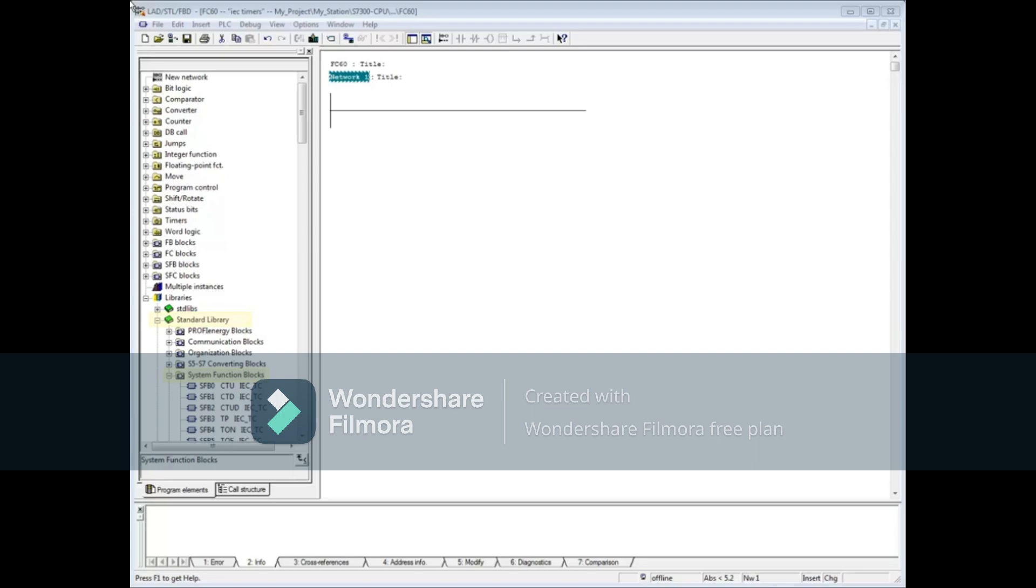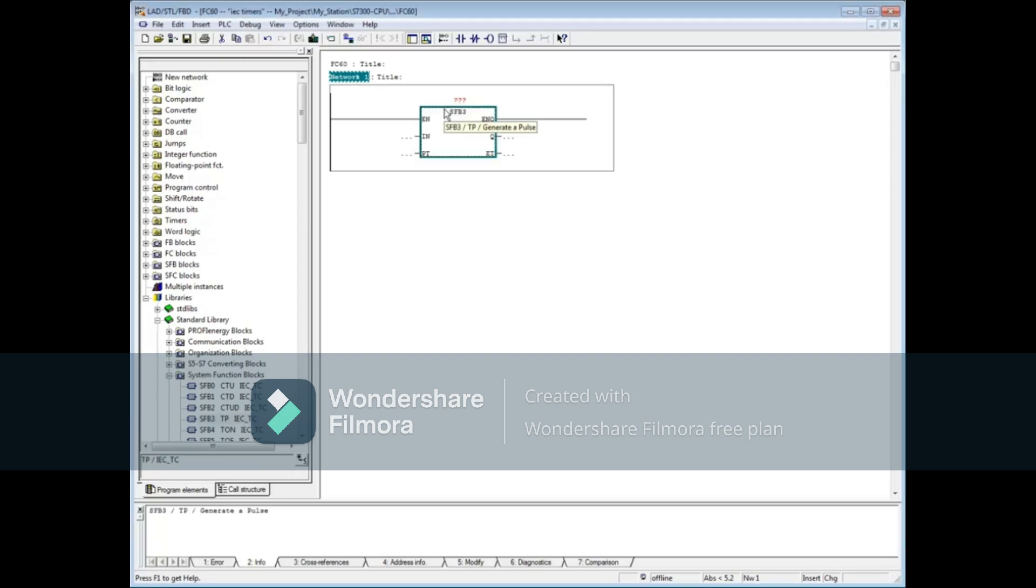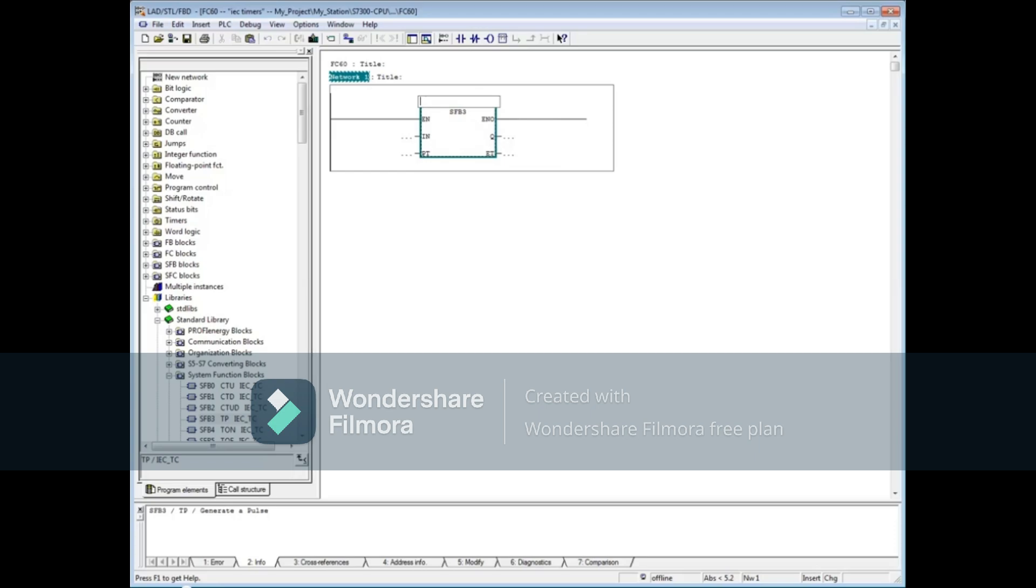Drag the pulse timer SFB3 to Network1. Since this is a system function block, a data block is required. Click on the three red question marks. Type the letters DB followed by a data block number that does not exist in the Blocks folder of the project.